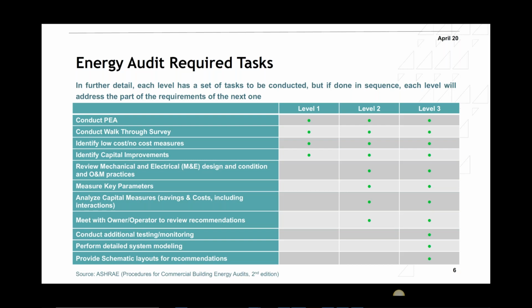Conducting the walkthrough survey. A walkthrough survey is basically going to the building, asking questions of the O&M personnel, checking how things are being done. If there's a BMS, you'd look into that. Normally, no measurements are required within level 1. Then you would identify the low cost and no cost measures, and then identify capital improvements, let's say like change of chillers, change of pumps, anything that really requires a lot of money to change.